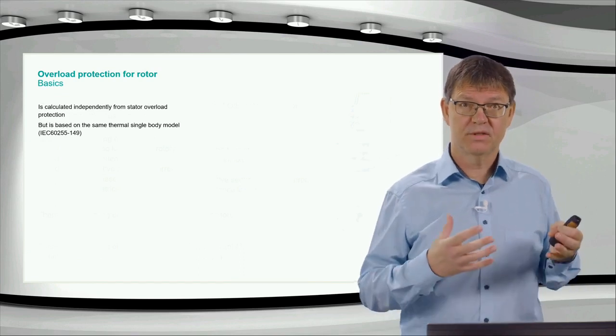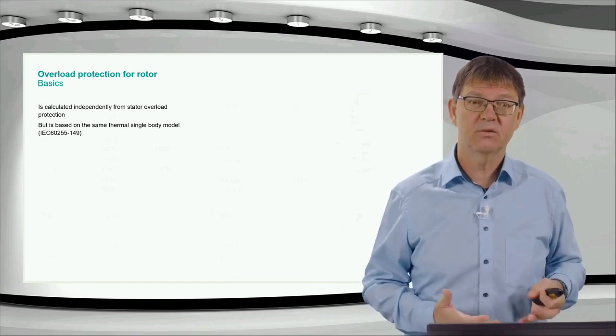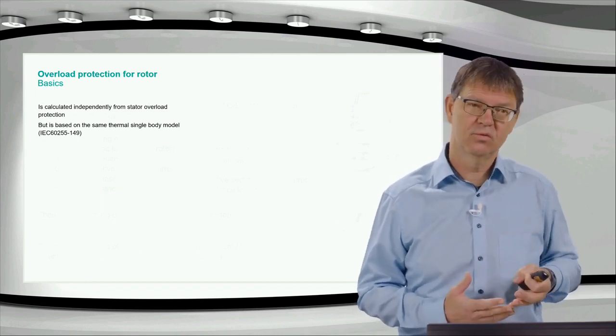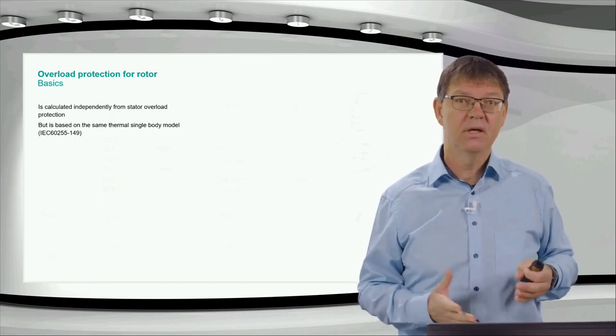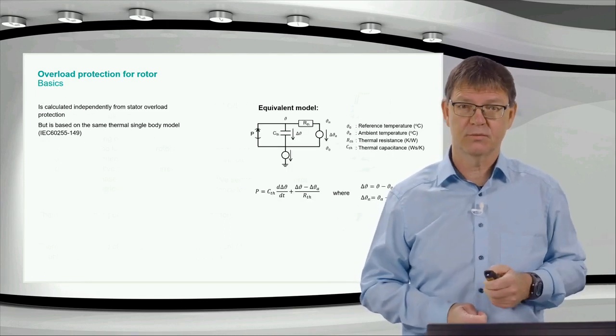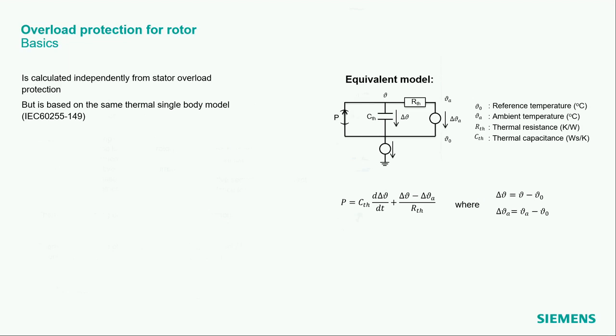However, what we use here for the rotor is based on the same thermal single body model, according to, you see the IEC number there, as we use it for the stator overload protection function. Here is this equivalent model. I will not go too much into detail. It's called single body model because we have one thermal capacitance here and a thermal resistance.